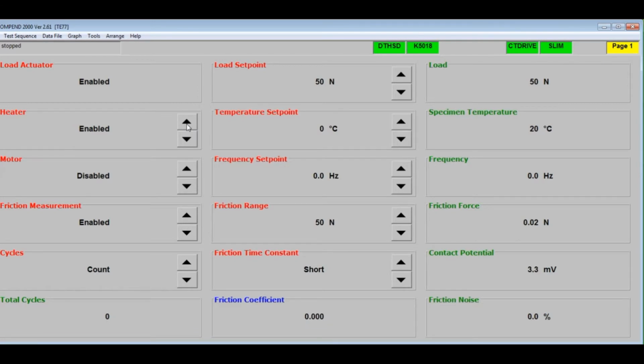The fixed specimen heater can now be enabled by clicking the up arrow on the red heater box. The temperature set point can now be set in just the same way as the load set point, using either the up and down arrows or by double clicking on the box and entering a value with the keyboard. The temperature as sensed by the thermocouple in the side of the specimen bath will be displayed in the green specimen temperature box.